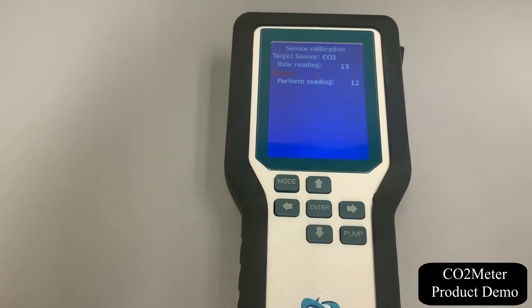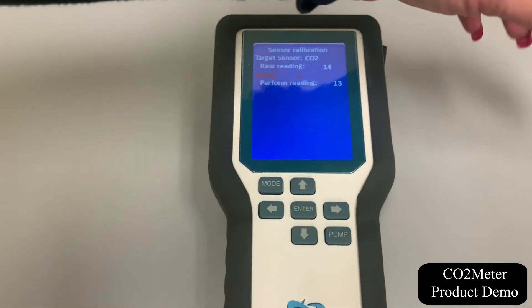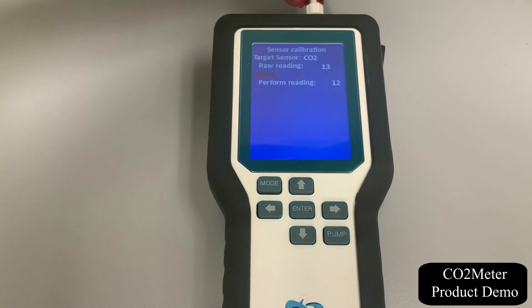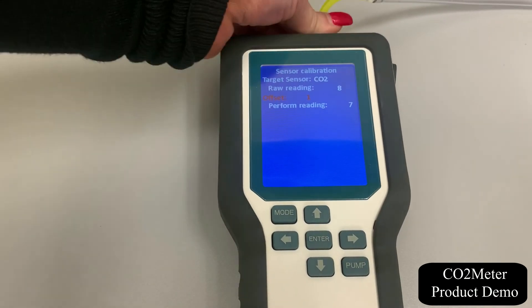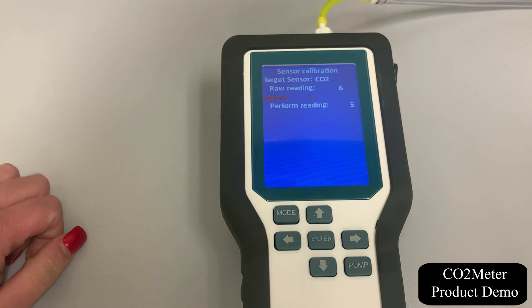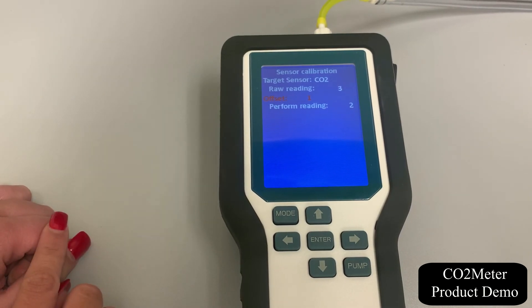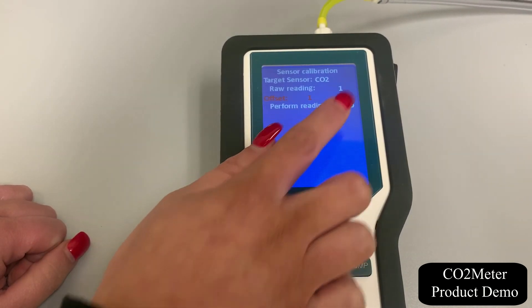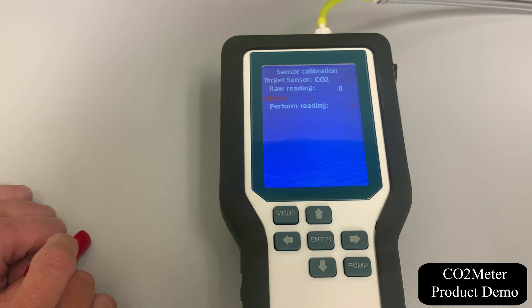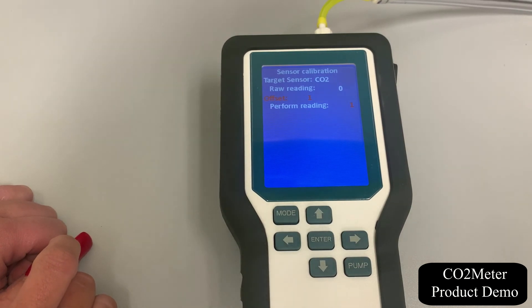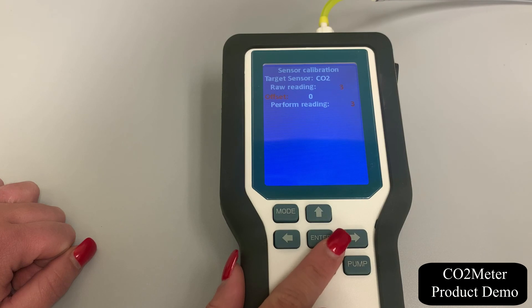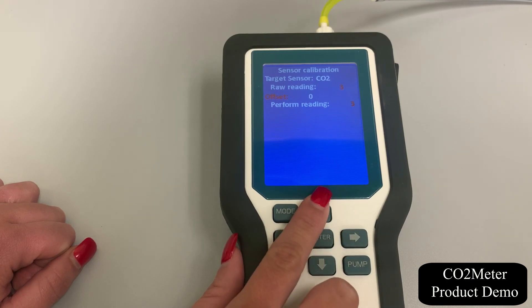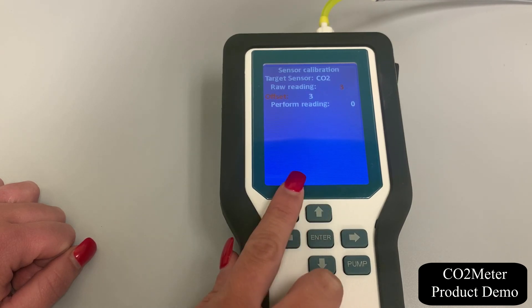Since this device only uses CO2, we have highlighted our CO2, and we have temp and RH present. Press enter to select the desired sensor — ours being CO2 — and highlight offset in red. Next, press up and down to adjust the offset value to calibrate the sensor. The offset value should be the difference between the raw reading and the performed reading. Finally, press enter when the performed value is correct and at zero.